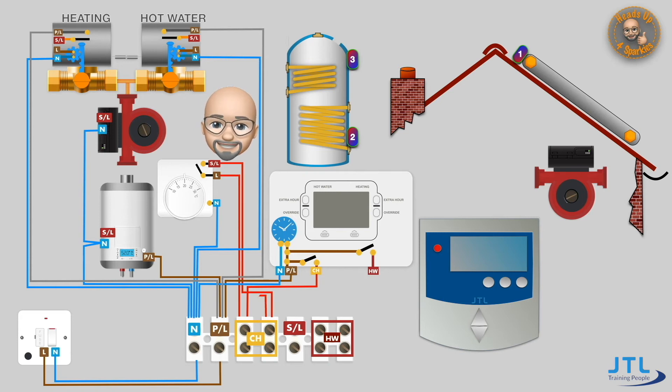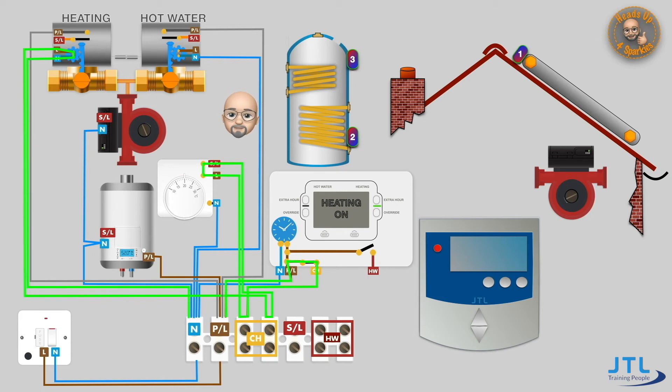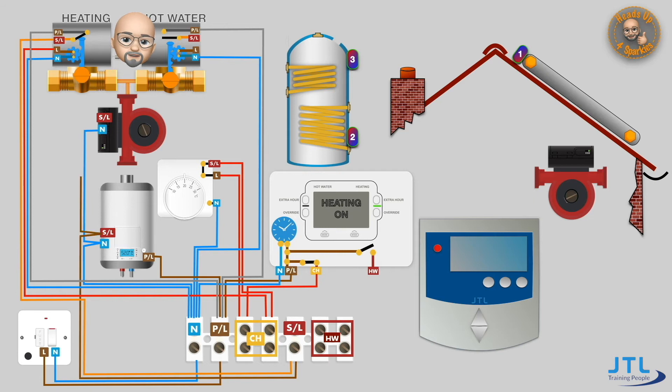Now let's install all the switch lines for the central heating system. The detail of this system is explained in our S-plan heating systems video, but we'll recap the basics here. With the programmer calling for heating, its switch closes and the system looks to the room stat to see if heat is required. When the room stat is calling for heat, this completes the circuit to the motorized valve for the central heating. Once the motorized valve is energized, it opens and closes the micro switch, switching the permanent live grey onto the switch line orange. This is wired back to the wiring centre and connected to the pump and boiler, so both fire up and hot water is circulated around the central heating system.